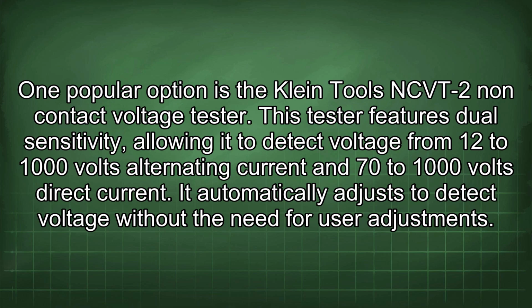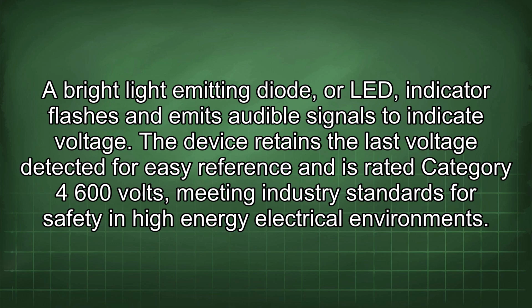One popular option is the Klein Tools NCVT-2 non-contact voltage tester. This tester features dual sensitivity, allowing it to detect voltage from 12 to 1000 volts alternating current and 70 to 1000 volts direct current. It automatically adjusts to detect voltage without the need for user adjustments. A bright light emitting diode, or LED, indicator flashes and emits audible signals to indicate voltage. The device retains the last voltage detected for easy reference and is rated Category 4 600 volts, meeting industry standards for safety in high-energy electrical environments.